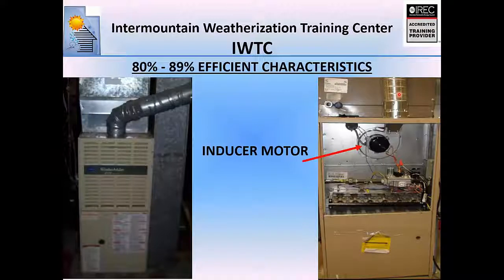I've seen furnace techs with a lot of experience, they've been around for years, who had the misconception that this inducer motor on this furnace actually pushes those flue gases out. It does not. This still depends on natural draft. And back to Matt's point, this can backdraft. If you get a CAZ that's negative enough that it overcomes the effect of this inducer sucking air and fuel into these burners, it will backdraft right back through the combustion chambers and start spilling out of these burners.